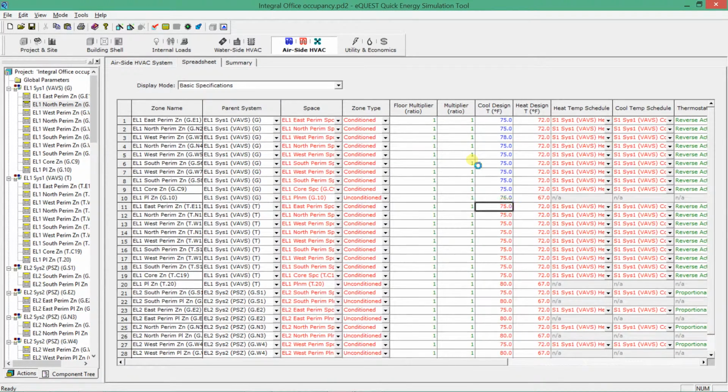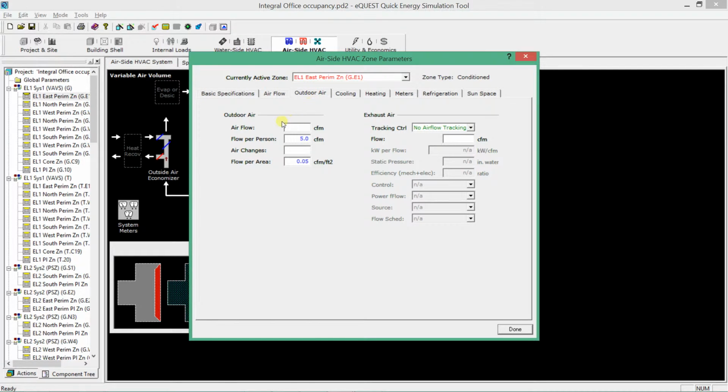All right, I'm not gonna do this for too long, otherwise we'll be here all day. So anyways, you get the idea, that could update. So let's go back to ventilation. Last thing for ventilation. So if you might remember earlier, I said in a video, eQuest is unlike the ventilation standards in that it does not add the different components of fresh air together to get the total fresh air. It just looks at all of these and the number of people in the area, and it picks the highest one. And that can make it very difficult for us to actually put in changing values that look like 62.1 that we're used to using when we really need to add up the total of those.